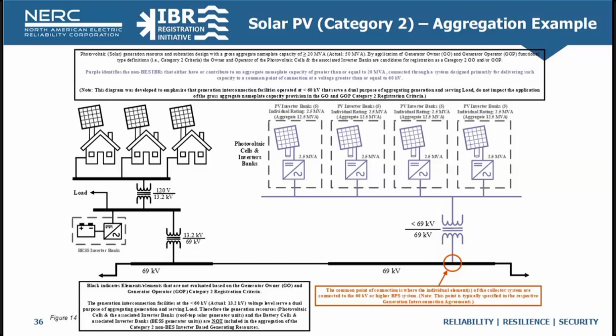Well, first of all, I would hope the objective isn't to build a facility that's just a hair fraction under the requirement for registration, but that's beside the point. It has to do with the interconnection of facilities and their purpose. If the facilities are designed—and the language used is a system designed primarily for delivering capacity—so if the facilities that are part of the collector system interconnecting the generation were constructed solely to aggregate the generation and deliver it to the bulk power system, then that gets aggregated. Making a statement that it's used for serving load isn't really applicable; it really has to do with how those facilities are designed and what their interconnection purpose was.